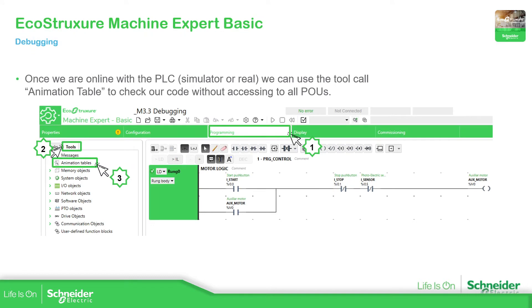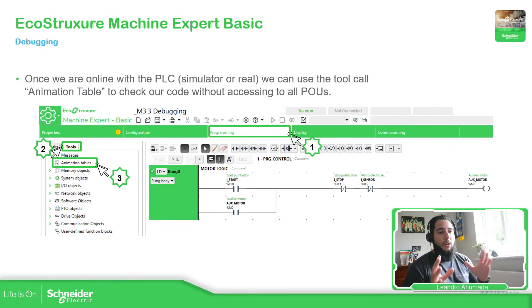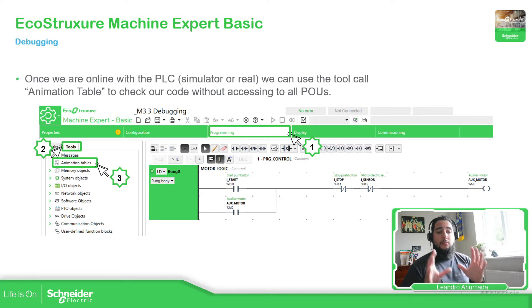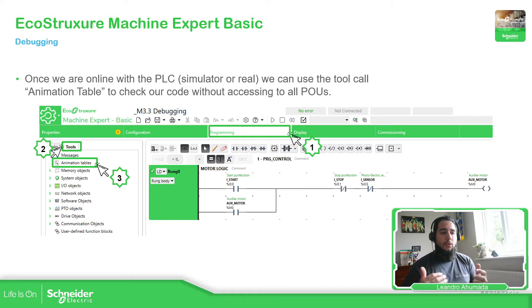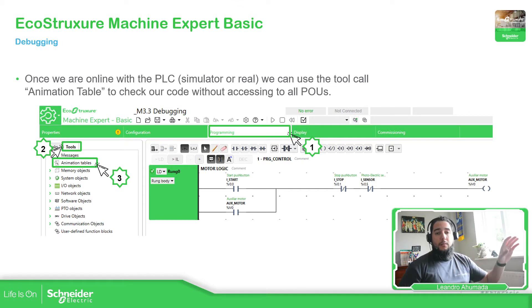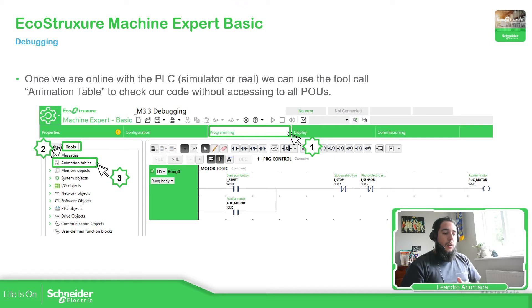What we're going to see in this presentation is what we call the animation table. In this animation table we can create a table where we can define all the variables that we want to see. So instead of using the ladder view of the code — where the program is probably divided in different POUs or different parts of the same ladder — we can use this table to see all the variables we want in one place. That's the advantage.